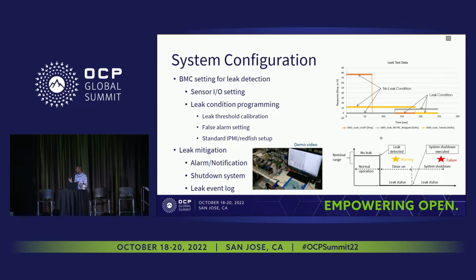So because I'm focusing only on the server level, what we did is just these 3 actions as a mitigation plan. One would be when a leak is detected, trigger an alarm, send a notification to the data center operators, and safely shut down the system. And maybe some applications might put a little timer in, instead of immediately shutting it down. That gives time to the data center engineer, maybe to troubleshoot without stopping whatever workload is running. But that's left to the discretion of the customer. And then, of course, you have the event log to go back to, and you can use that for troubleshooting.